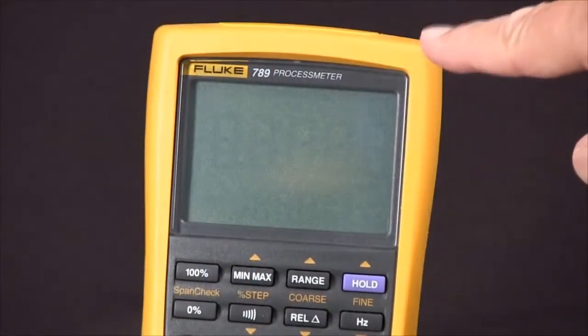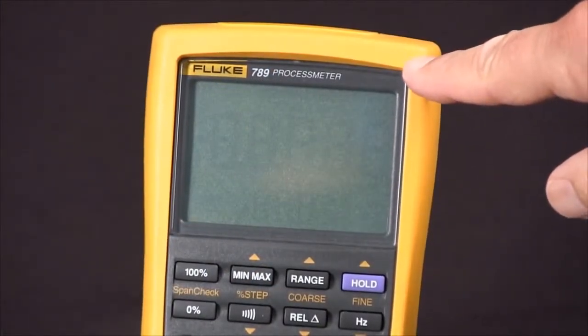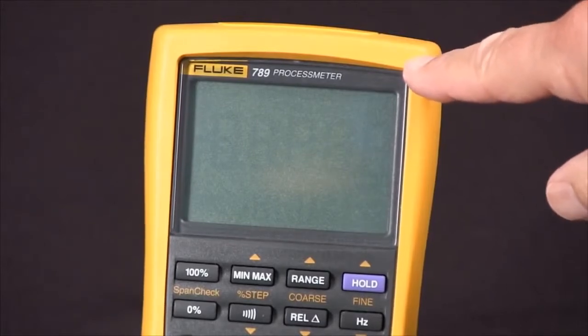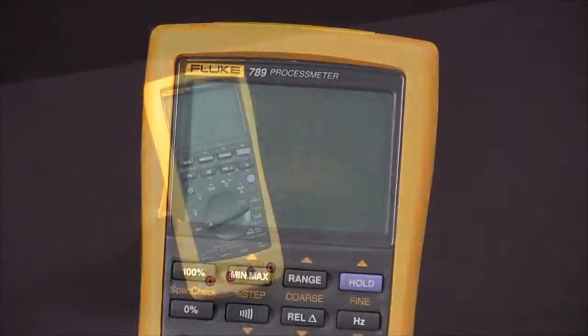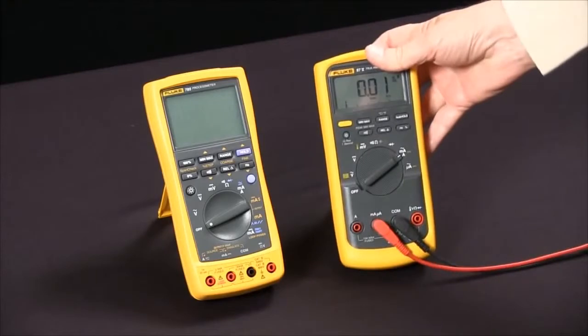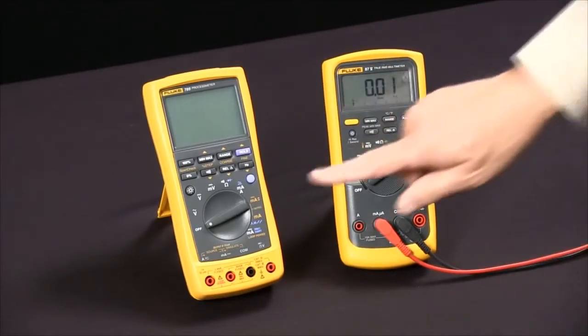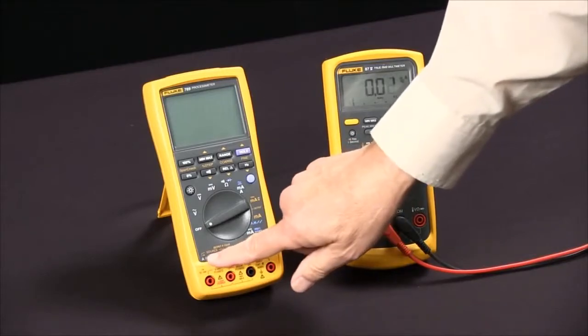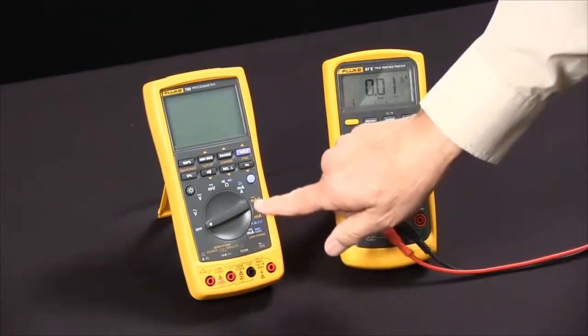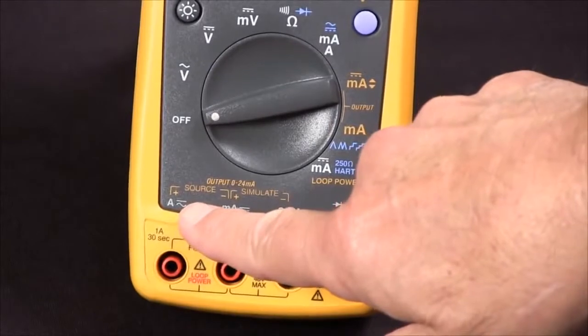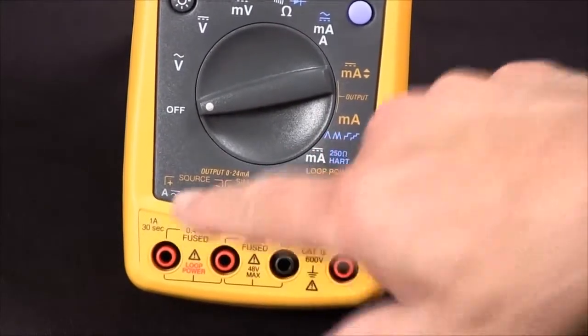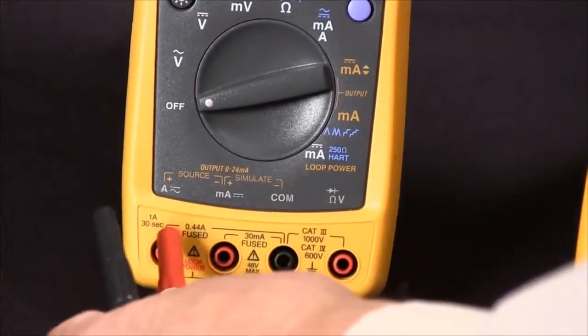To source 4 to 20 milliamps DC current with our Fluke 789 process meter, we're going to use a digital multimeter to measure the current that we're sourcing. You'll notice everything that has to do with sourcing is in orange. We're going to come over here to the source plus and minus output and attach our meter.